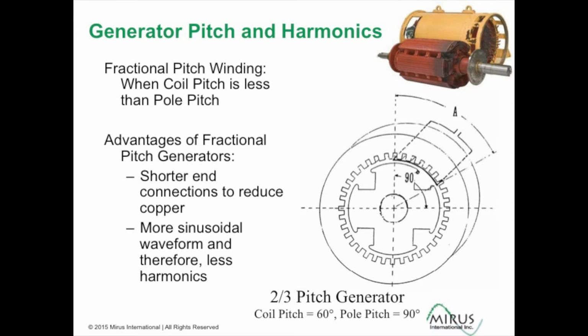But most generators are built with fractional pitch windings. And the main reasons for this is that you can reduce the copper in the windings by going fractional pitch, so the length of the winding is much shorter and doesn't go the full 90 degrees. And also, it turns out that fractional pitch windings actually are more sinusoidal than full pitch configurations, so there's less harmonics that's created. So this example shows a 2/3 pitch where the coil pitch is 60 degrees, the pole pitch is 90 degrees, and that equals 2/3 pitch, and this generator would be a 2/3 pitch generator.